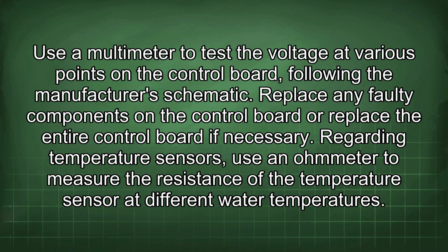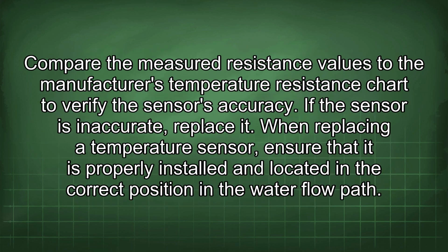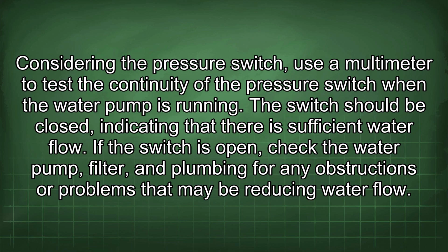Regarding temperature sensors, use an ohmmeter to measure the resistance of the temperature sensor at different water temperatures. Compare the measured resistance values to the manufacturer's temperature resistance chart to verify the sensor's accuracy. If the sensor is inaccurate, replace it. When replacing a temperature sensor, ensure that it is properly installed and located in the correct position in the water flow path.